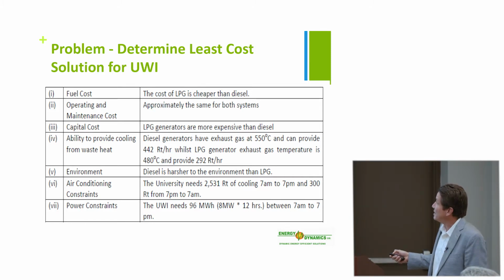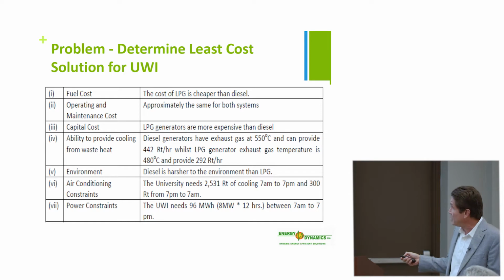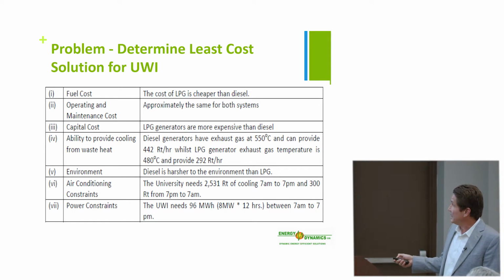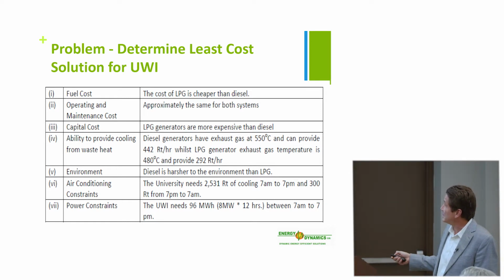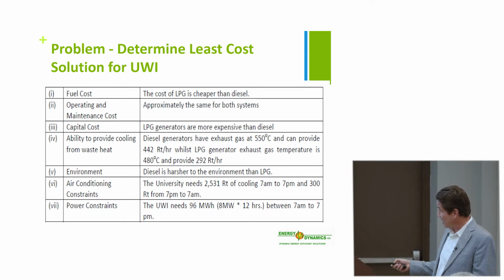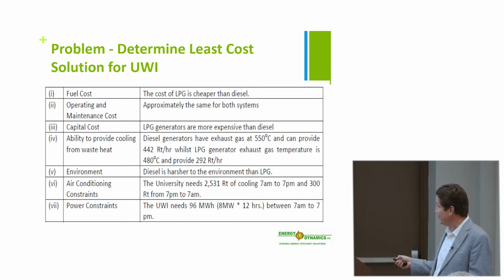For operator maintenance cost, we assumed both diesel and LPG were the same. Capital cost, the LPG generators are more expensive than diesel. For the ability to provide cooling from waste heat, diesel generators have exhaust at 550 degrees and can provide 442 tons per hour, while LPG generator exhaust is 480 degrees and provides 292 tons per hour. As for the environment, diesel is harsher than LPG, and of course LNG is even the best.